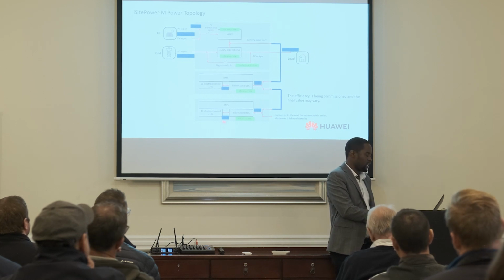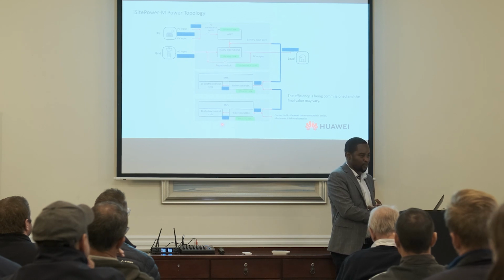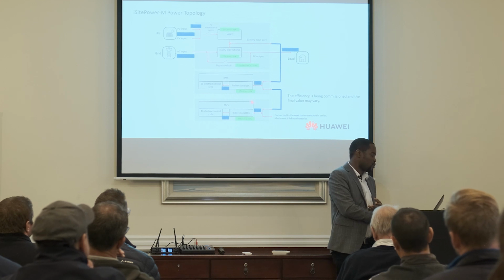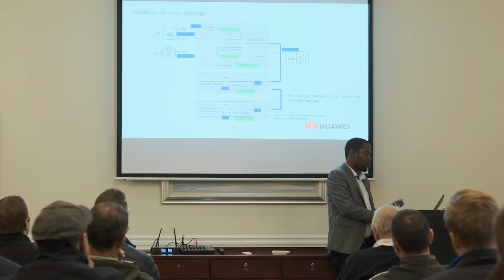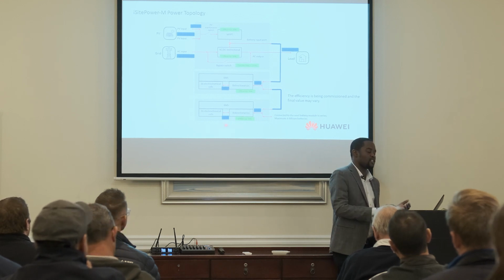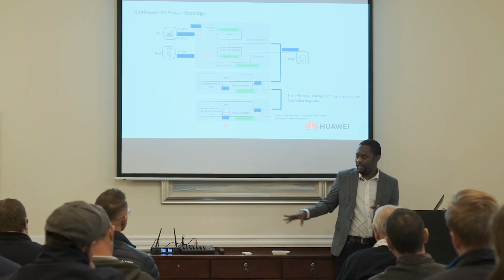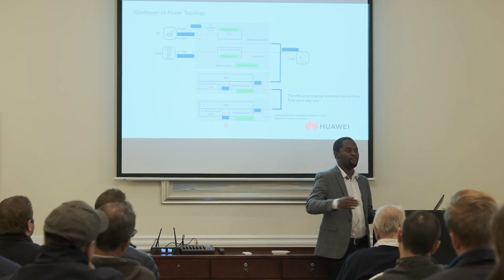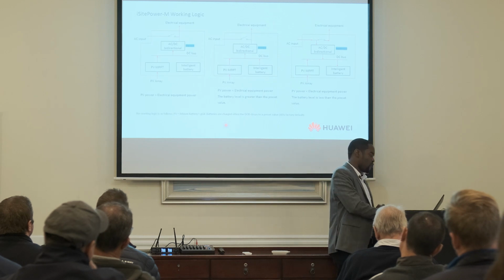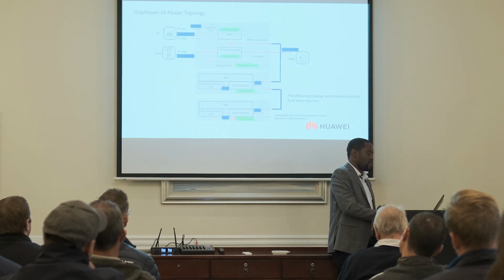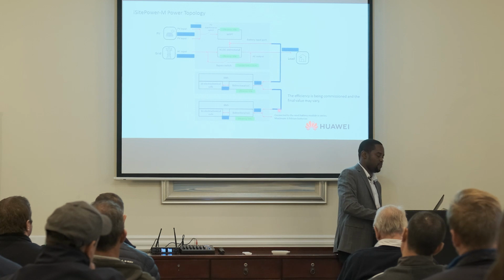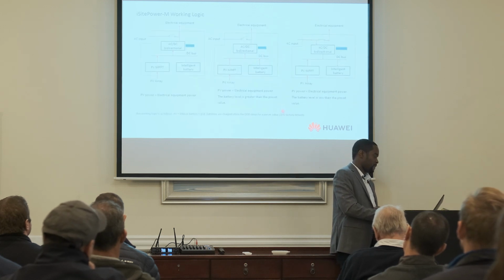Then if you look closely here, you will realize that these battery modules are actually low voltage modules. It's 51.2 volts here, but it goes through a bidirectional circuitry, which is actually a voltage booster or a transformer. So you are boosting that 51 volts to 400 volts, but the boosting is happening in the battery pack, in the battery module, before the MPPT or before the common bus bar. So you get more efficiency, more stability on the system because the voltages are matching.